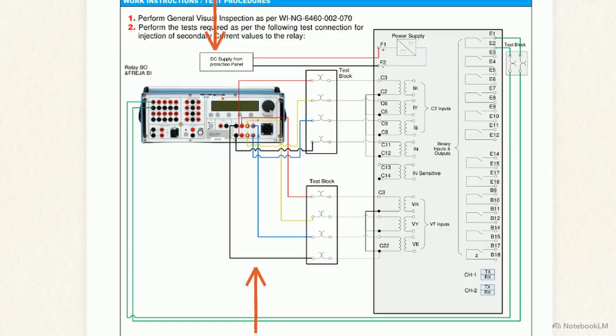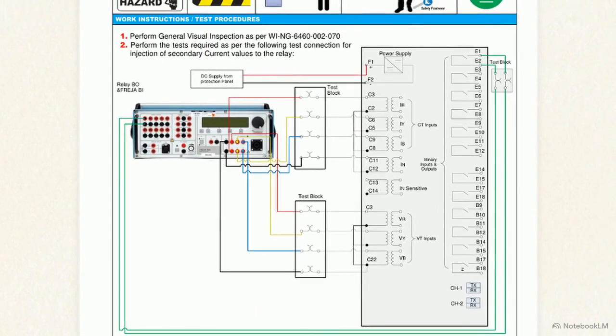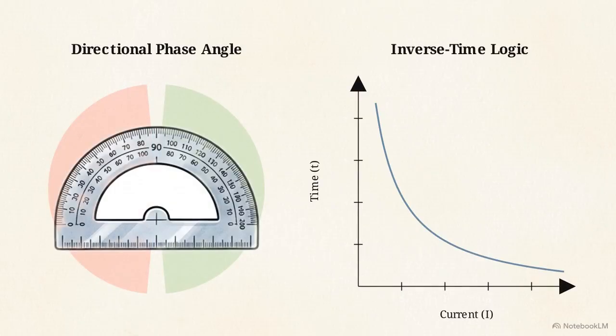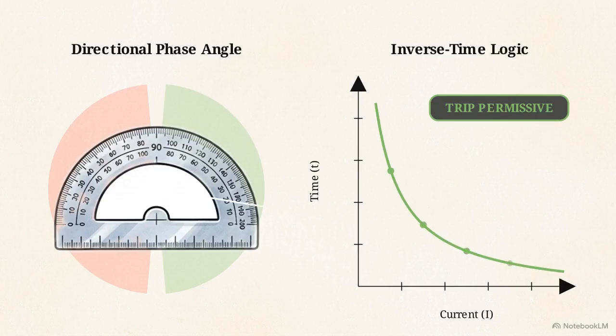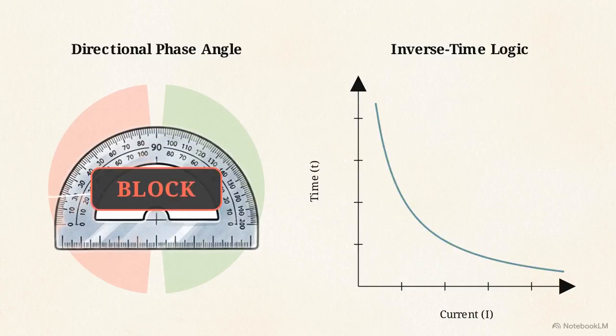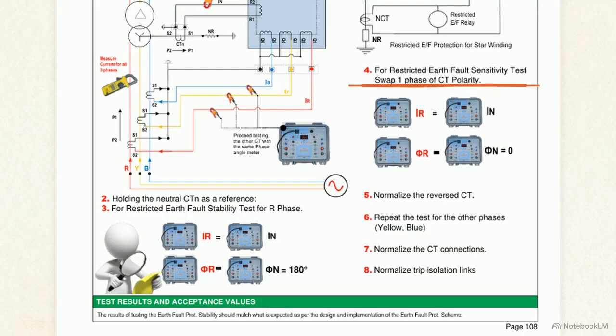Technicians must simultaneously simulate current magnitude and a polarizing reference voltage. By comparing the two, the relay calculates the phase angle to determine the exact direction of the fault. The acceptance criteria require the injection set to push the phase angle through forward, reverse, and undefined zones. The relay must trip or block as mapped on its inverse time curves, isolating faults downstream while ignoring currents feeding back into the grid. In this restricted earth fault schematic, we observe the sensitivity test.